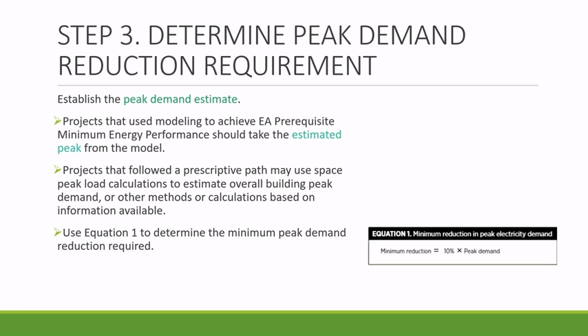Step 4 is to develop strategies for peak demand reduction. Project teams may reduce peak demand by modifying consumption from various end-use systems such as HVAC and lighting. One strategy to reduce demand is to make global temperature adjustments to increase cooling set points or decrease heating set points for an entire facility for a given period. Facilities managers may find that some occupants prefer the temperatures under demand response events, indicating the possibility of making permanent changes to the set points.